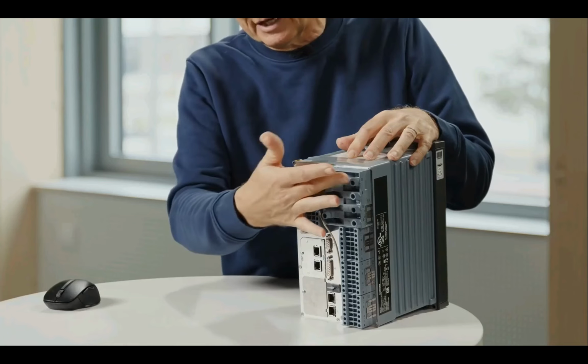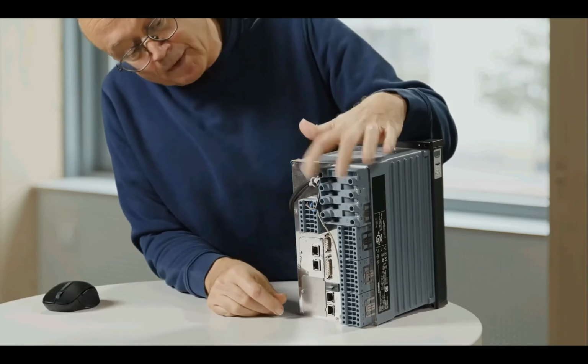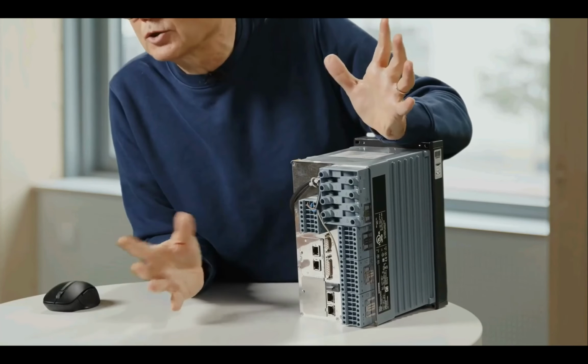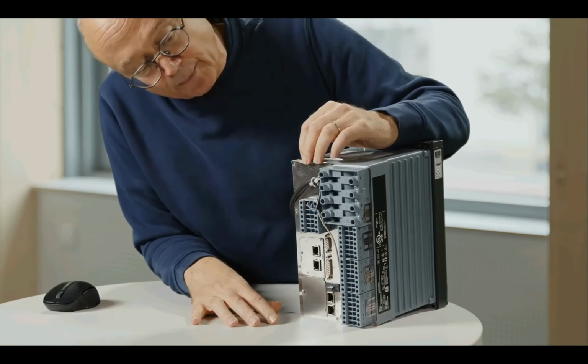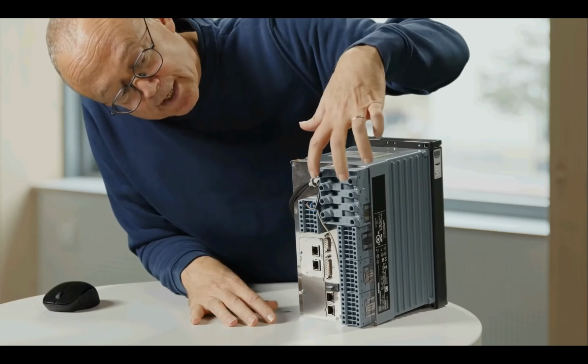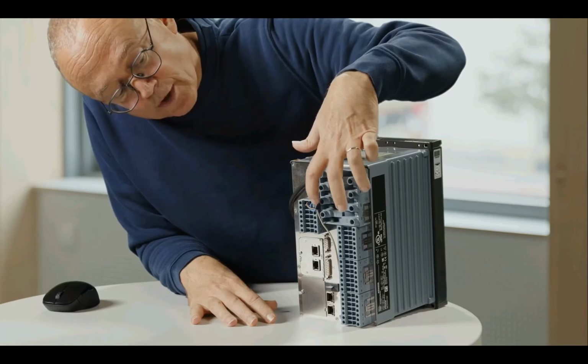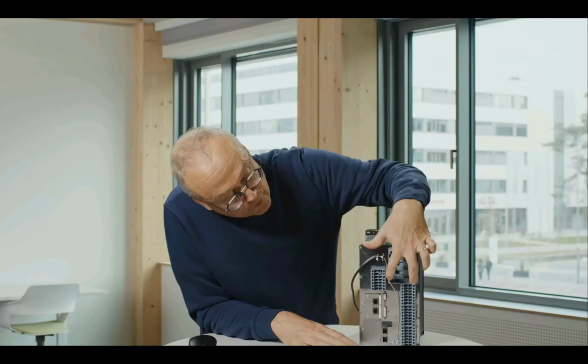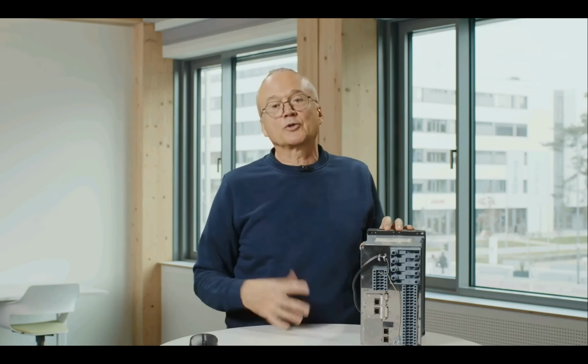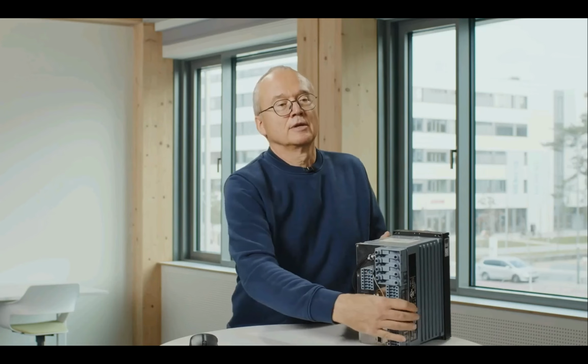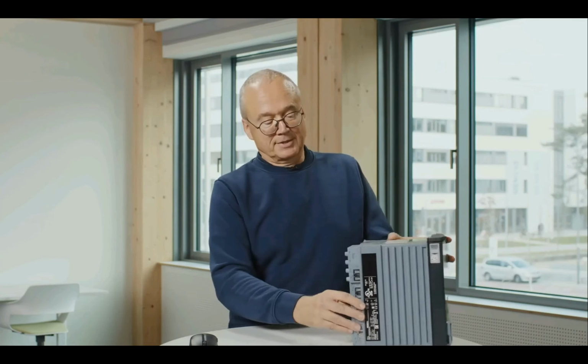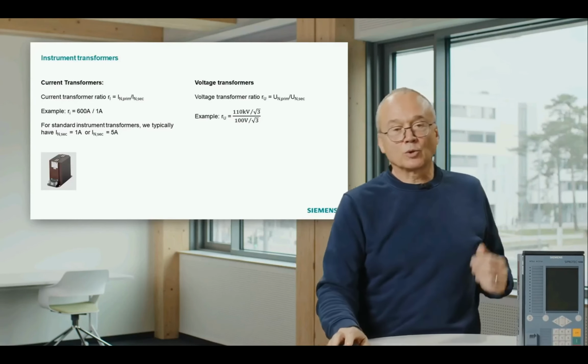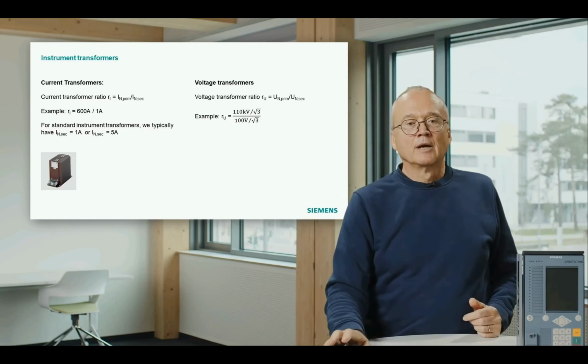And you can imagine for that you need bigger screws, and of course you also need sufficient cross-section. What you also see here is you have phase 1, 2, 3, and you have the 4th pair of inputs for the Holmgreen connection or for a sensitive core balance CT to connect it. That was the current transformer.